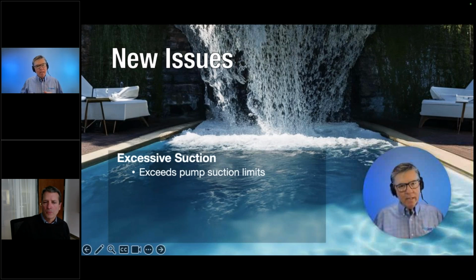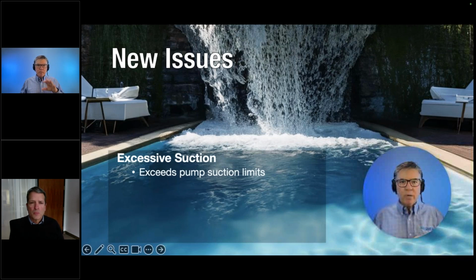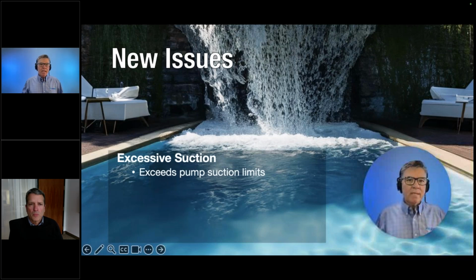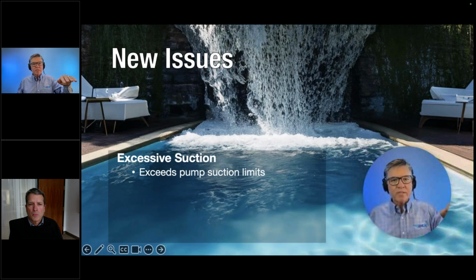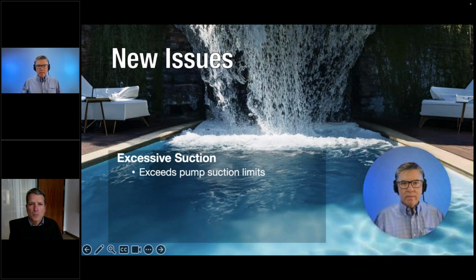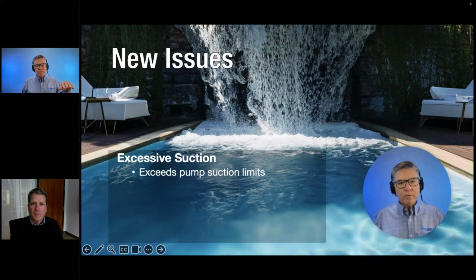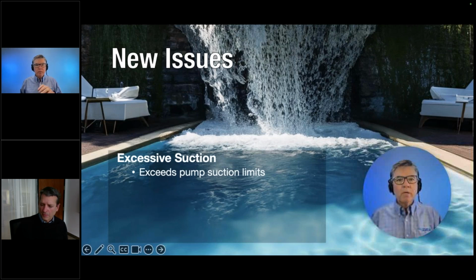So what happens is the impeller, centrifugal force, flings the water sand particles, right, and boosts it into pressure, and then the atmospheric pressure pushes the water from the pool to the pump. And if you get the pump too high, in case you doubt the physics of this, just go install a pump at 35 feet and see how well it works. It will never work because atmospheric pressure, even at a full vacuum, which a pump's not capable of, is only 33 feet. So if that pump's at 35, it will never, anywhere on this planet, ever get water because we only have atmospheric pressure. And the higher the elevation, we used to see lots of problems with in-floor cleaning systems in Denver because of cavitation on the pumps. And at the time, I had no clue what the problem was.